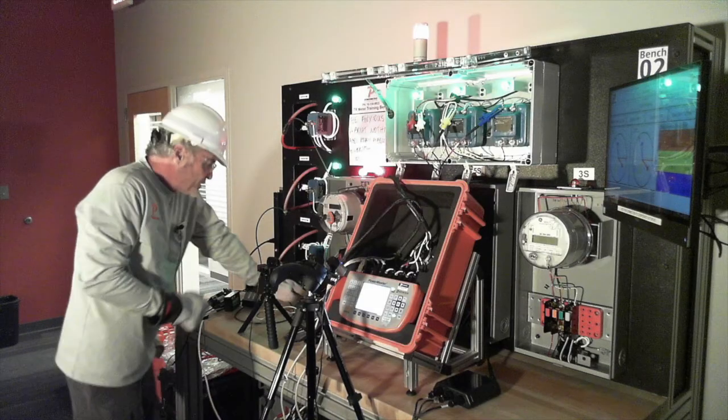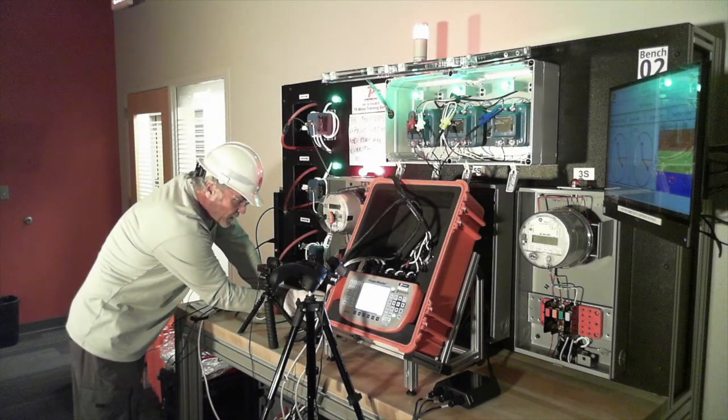On this particular test switch, this one's a little janky, so you've got to watch what you're doing. I've got my 3 shunts here, and I've got my voltages here, here, and here. You can see neutral, and all 3 of my returns are over here on the far right. So I need to go from the bottom of the return on A phase to the top of the shunt on A phase.